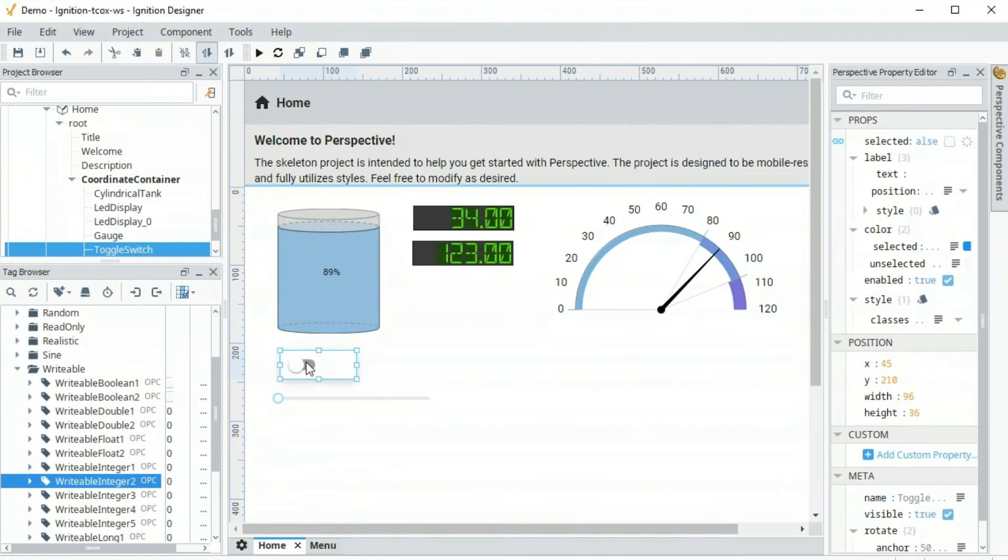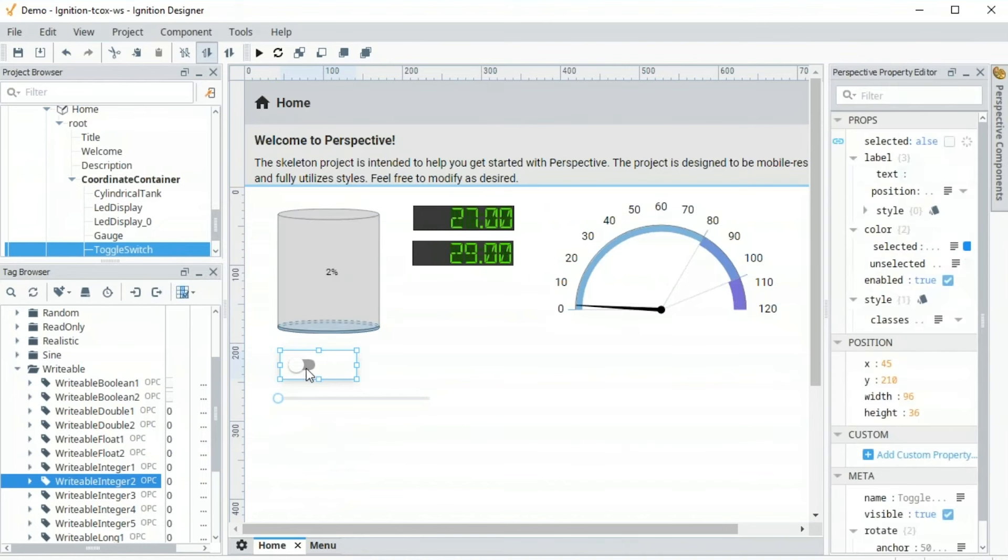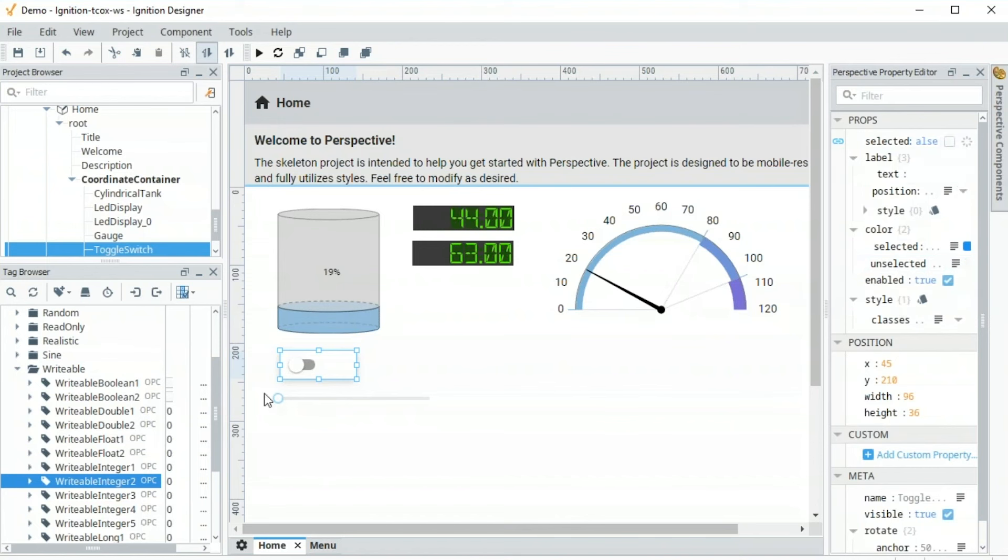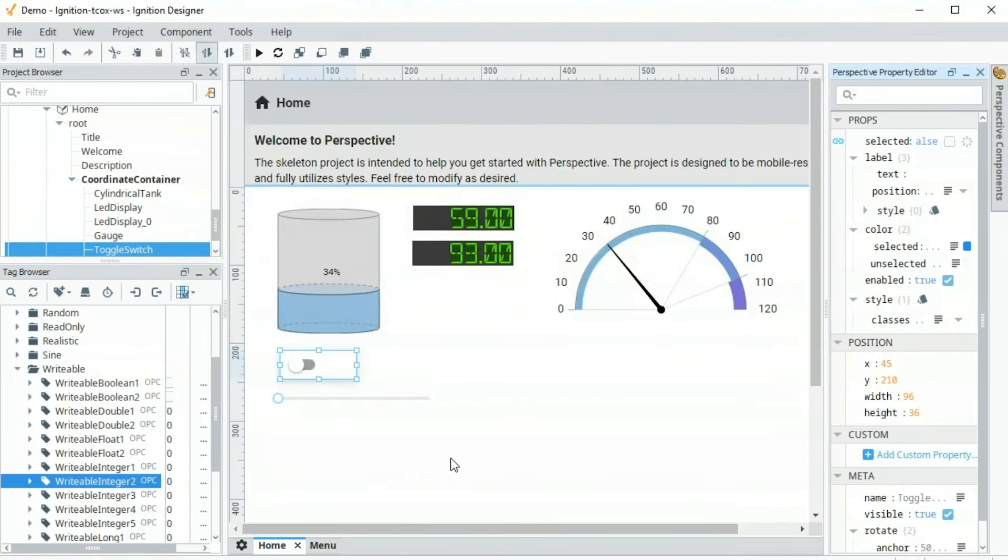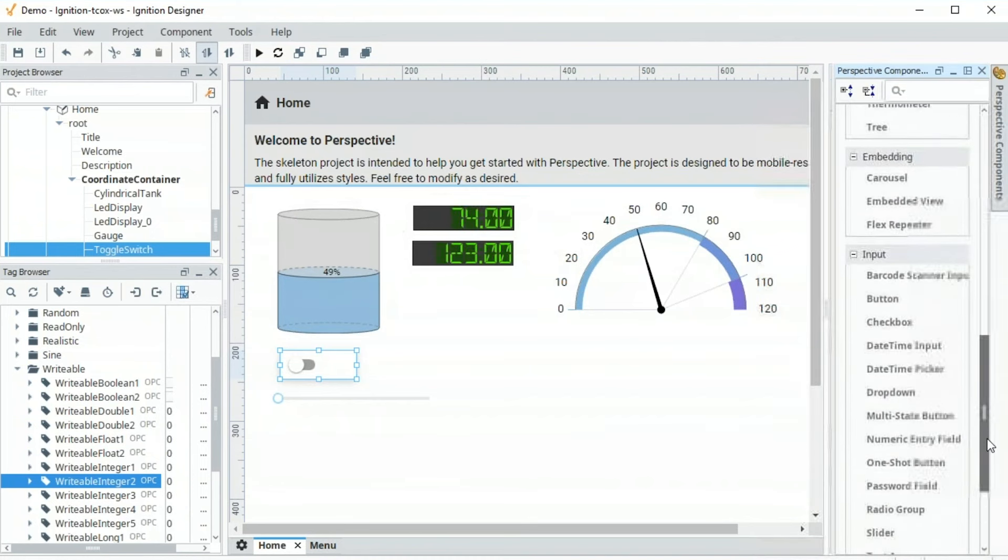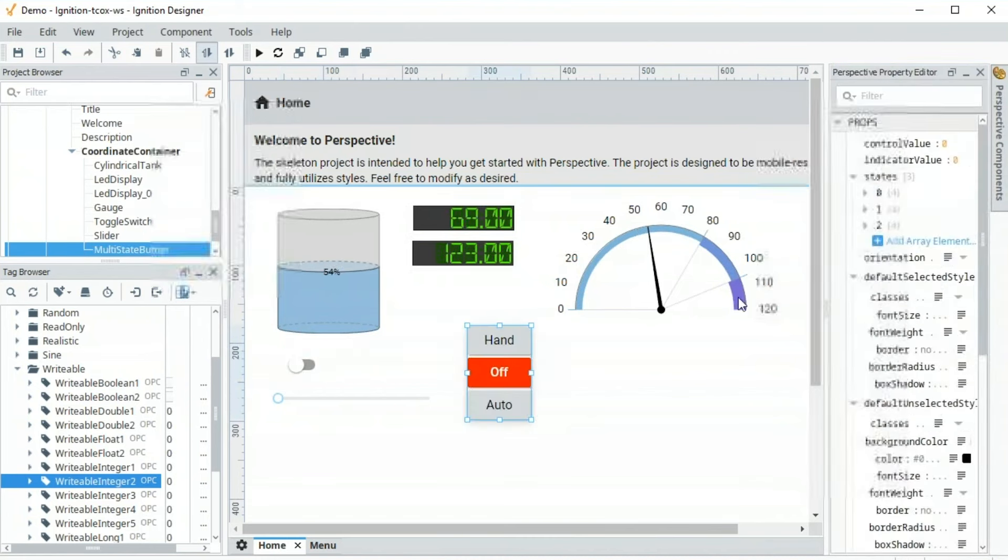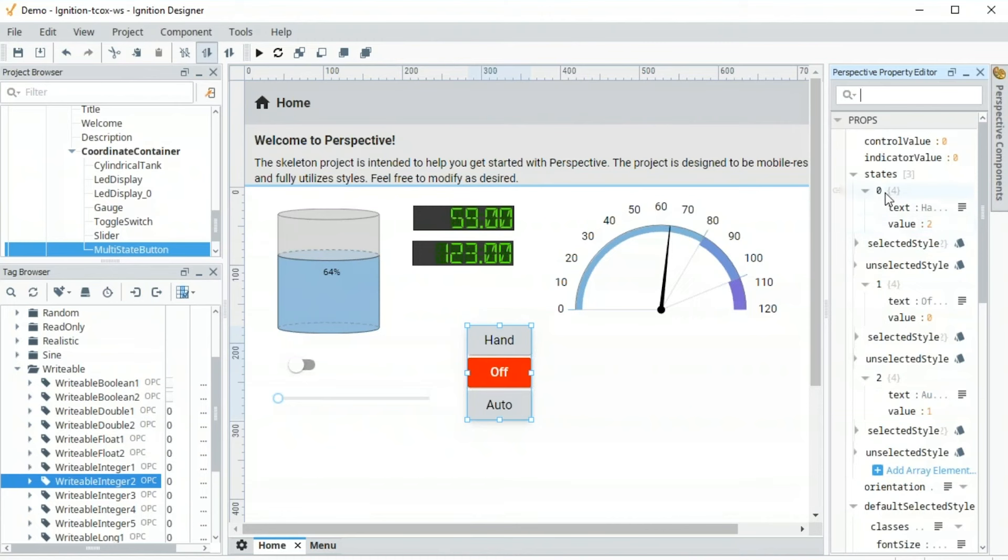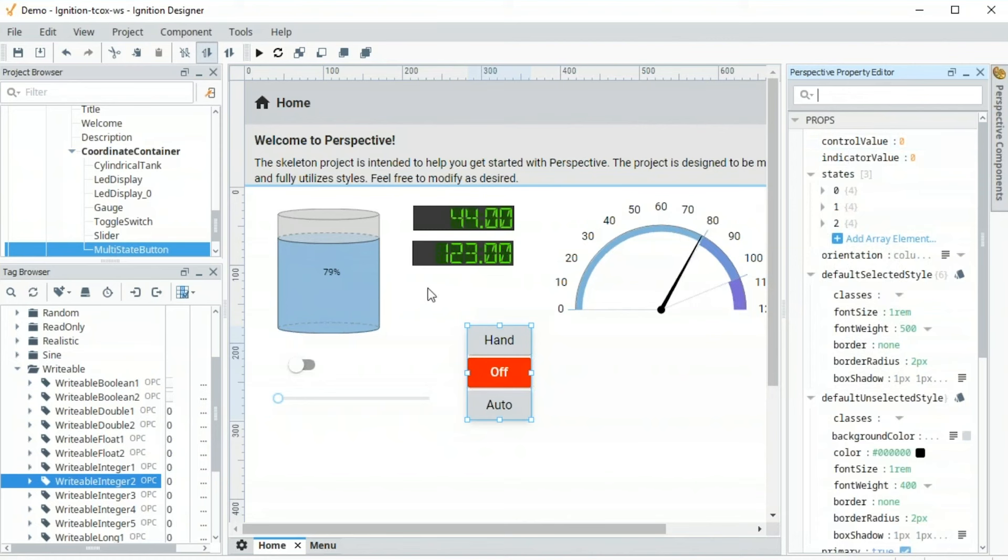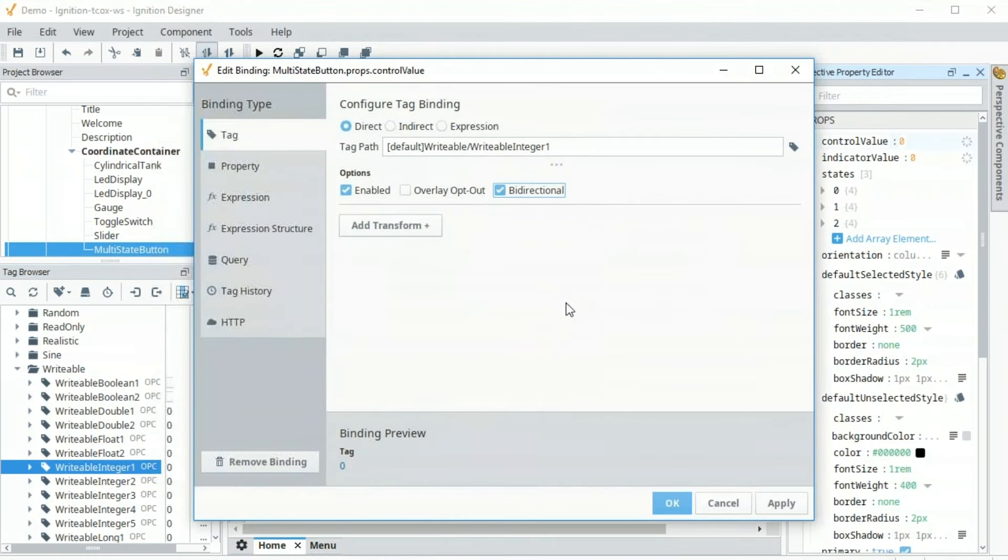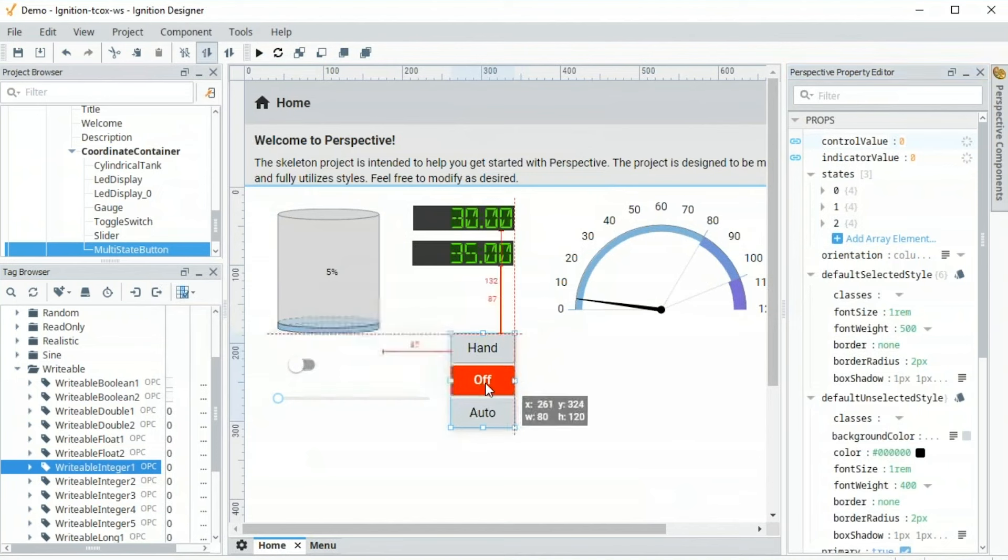Now these components that we have, there's a lot of different components that we can work with. You'll see them over here in the component set. And they all have properties for the way it looks and the way it behaves. And what we've done by drag and drop is link those properties to the tags. So this toggle switch you'll see is selected is linked to that tag. We can make it bidirectional if we want to write back to the PLC as well. Very easy to work with. There's a lot of components over here that we can bring on the screen. So let's go to our input and bring in a multi-state button, which by default is HOA. But you can change those states over here. So there's 0, 1, 2. You can just specify what you want those states to be. And now we can link the control indicator value properties to our tags. Let's take this writable integer 1, drag it over to the control value. And let's take this one and drag it to the indicator value. We'll make the control value bidirectional. Now we've got that built out.